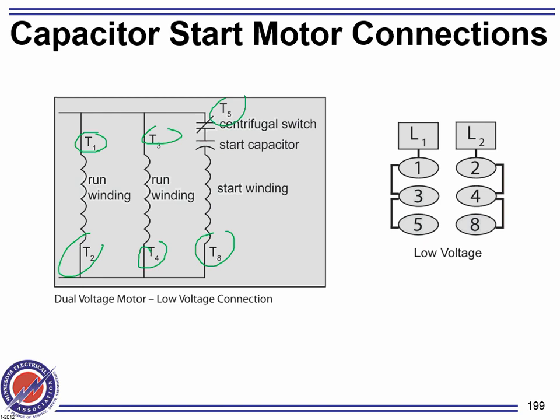Do you guys remember how we make low voltage? What do you do when you have coils? You make low voltage by paralleling them. To make high voltage, what do you do? Series them. In order to get low voltage, you tie all the odds together, all the evens together, and then you go to hot 1, hot 2. That will get you low voltage. If this motor has two voltages, 120 and 240, you tie all the odds together, all the evens together, and that gets you low voltage.